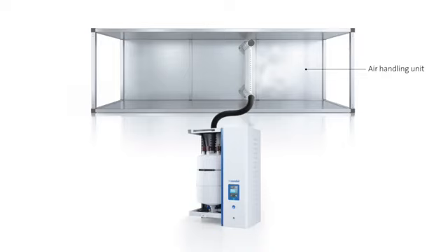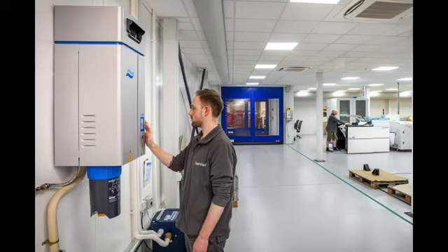So are air handling units not able to control humidity to start with? No, not always. A lot of AHUs are fitted with a space for a humidifier should one be needed, so they can be retrofitted if the need arises. However, sometimes even with an AHU in a building, there can be times when it's better to fit the humidifier locally. For instance, if humidity control is only needed in one area of a large building, it can be cheaper to use a single small direct room humidifier.